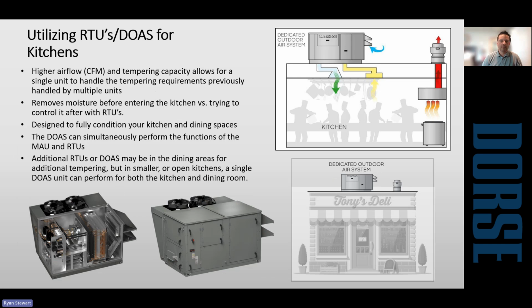So another option for makeup air is utilizing an RTU or a DOAS. This is something that's become more popular over the last few years because of the advances in these products. Now we have RTUs and DOAS that can handle conditioning full 100% outside air. The idea behind this is that rather than have a makeup air unit and an RTU, you have one unit that handles both the heating and cooling for the kitchen and the outside air.